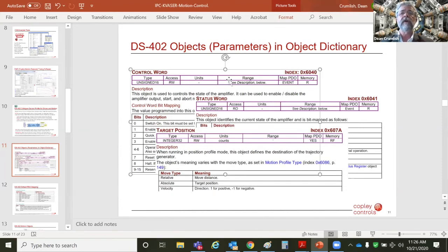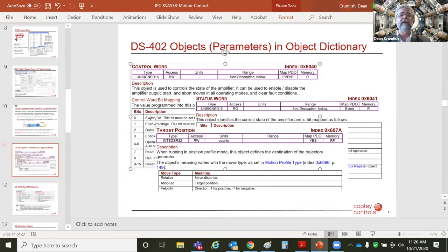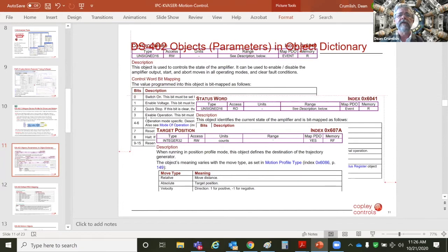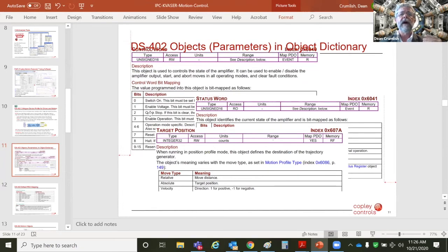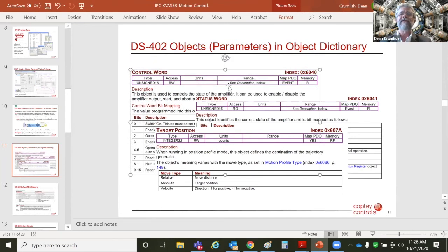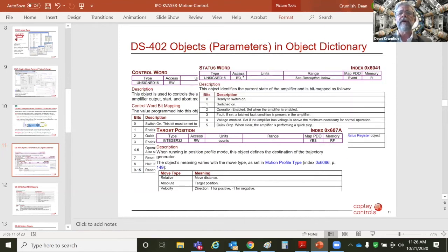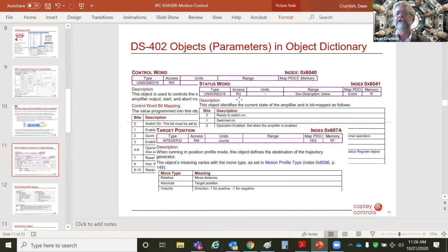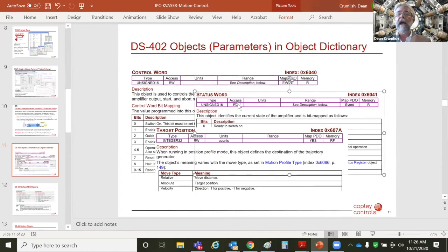And the software will also work on the control word, right? So the state machine: all the bits get set, you're switched on, you're enabled, you're not stopping, you go from pre-op to op, and you're in a mode of operation. The basic idea is the control word controls things. Bit 4 in the control word will update the trajectory and move to the target position. Then when the move is done, the status word bit gets set for motion done. I ask you to move and I'm waiting for you to move, and the status word will tell us when we're done.